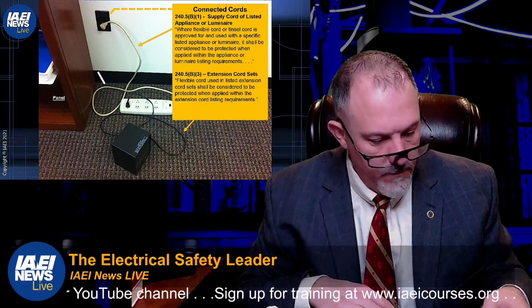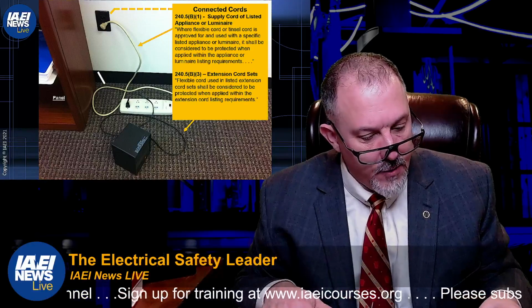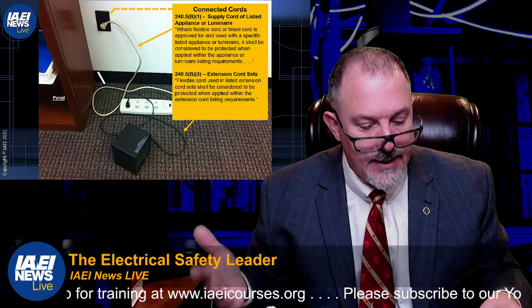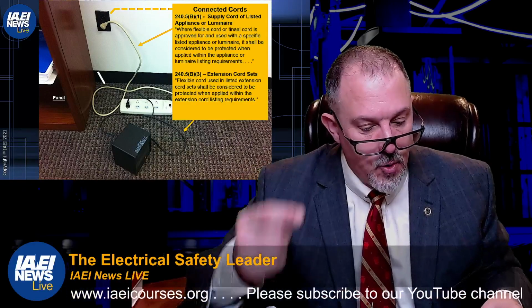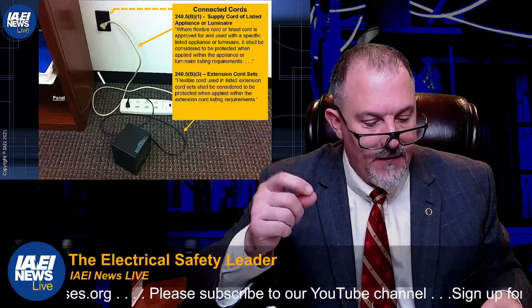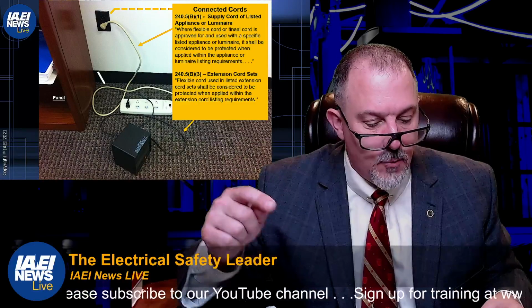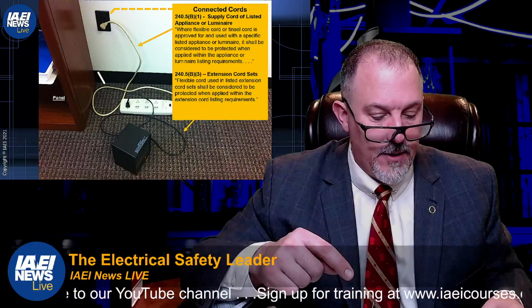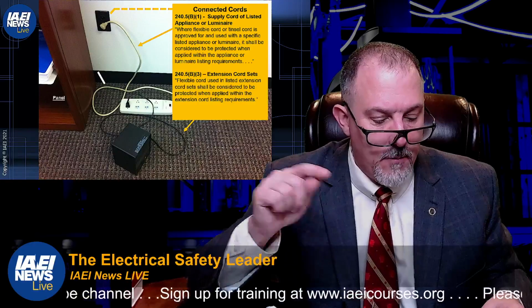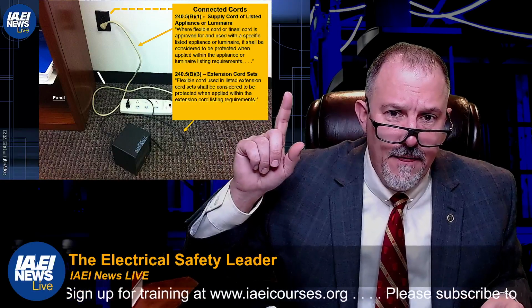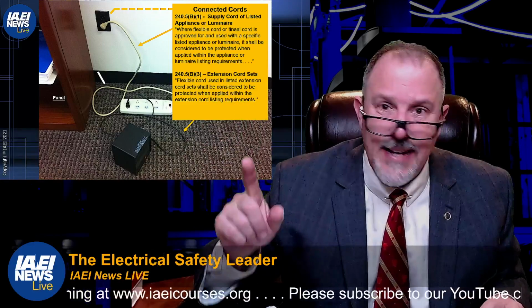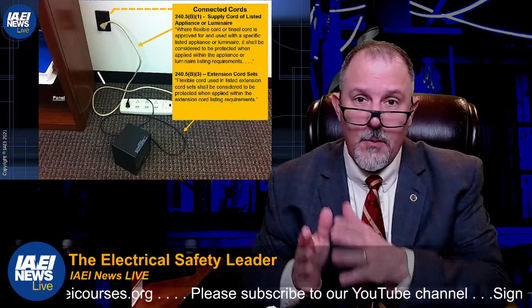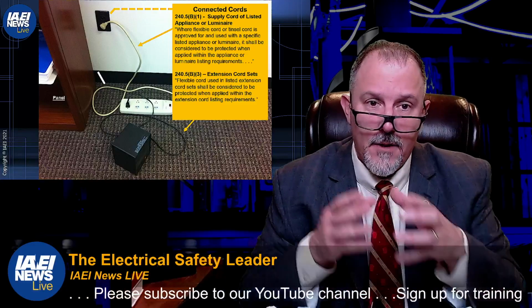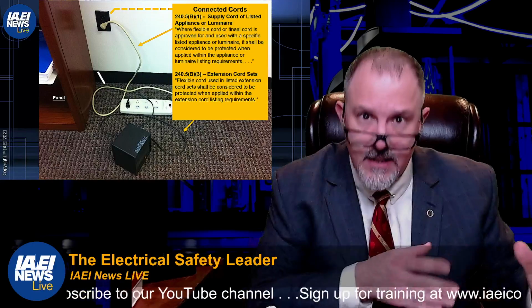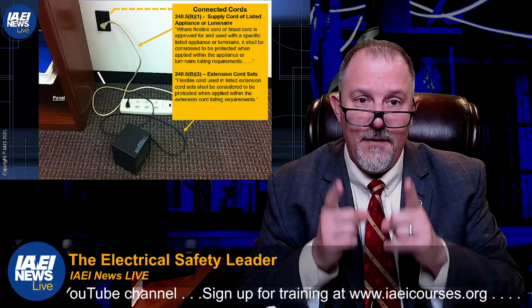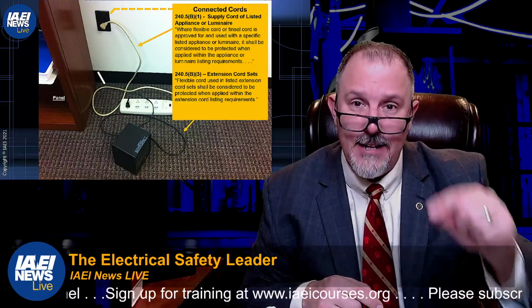240.5(B), branch circuit overcurrent. (1) Supply cord of listed appliance or luminaire: where flexible cord or tinsel cord is approved for and used with a specific listed appliance or luminaire, it shall be considered to be protected when applied within the appliance or luminaire's listing requirements. For the purposes of this section, a luminaire may be either portable or permanent. So the protection of that luminaire has nothing to do with the circuit breaker. The circuit breaker is not there to protect that luminaire. It is there to protect the branch circuit that feeds that luminaire. The protection of that conductor is applying it within its rating.